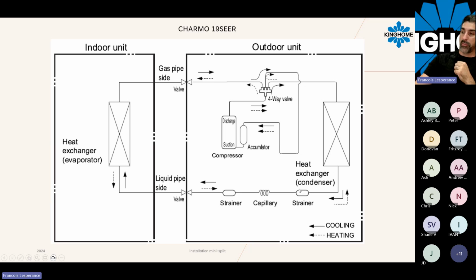That refrigerant will push through a strainer to protect the capillary tube, and then the capillary tube will be our metering device. Basically, the biggest difference between ductless and central units is that in a central unit, for example with our Ultranex series, the TXV is located at the indoor coil, so the metering device is located here. Now for ductless, all the metering devices are located at the outdoor unit. This is why the liquid pipe needs to be insulated: you will have low pressure on that part of the capillary tube, so it can start to have some condensation on it.